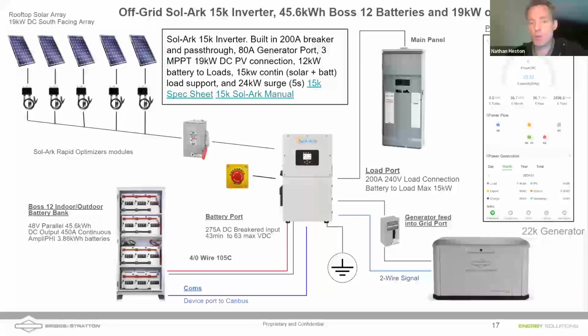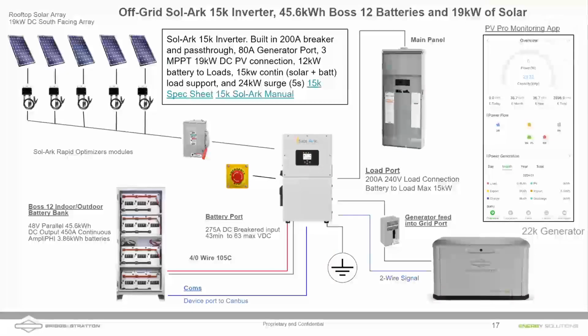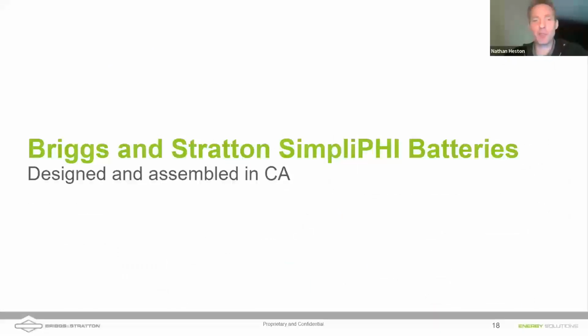And so keeping the two-wire start functionality of the inverter to control that generator is where I'm experiencing more of that challenge. And that's why I was suggesting that I would do it through the loads port. If you brought your generator in through the grid port, there are other complications as well in switching between it. So I do think that you could do that, but then you lose the two-wire start functionality, I believe, of the generator. But if it was that transfer switch, if it was off grid, that would be no problem. Which is why I kind of jumped to your other slide.